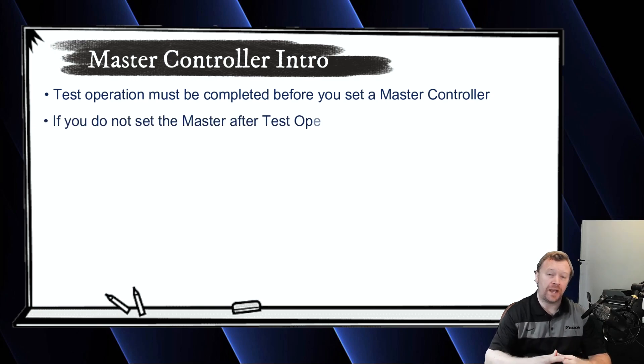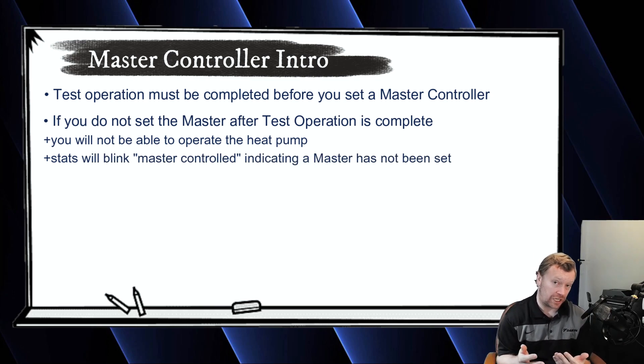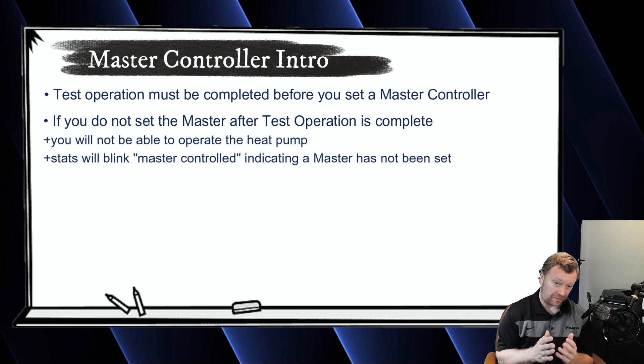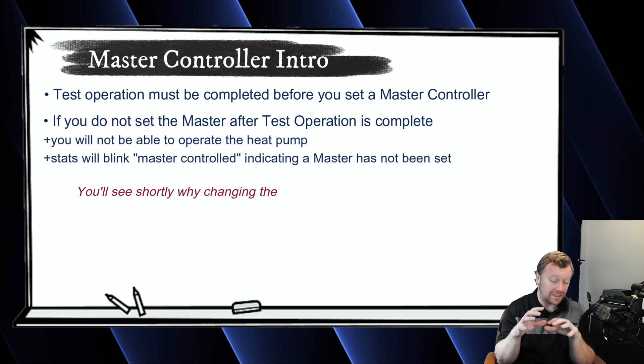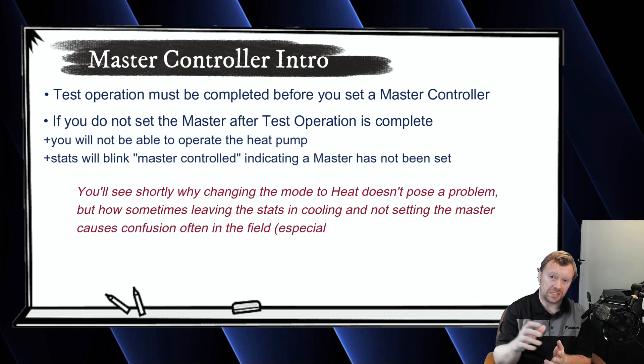If you don't set a master and you just turn on all the stats, they defaulted to testing cooling. So if you simply turn them on and don't change the mode, you only change the set point, the outdoor unit doesn't know who the boss is, so the outdoor unit will never turn on. I've had a few different jobs go down like this in the summertime, especially in my market, because that's when we cool — in the summer. We're cold in the winter in Seattle, so we always naturally change the thermostats to heat. In the summer, guys just see cooling as the mode out of test, and they think they're just going to turn it on, set the set point down to 67 or 68, and start operating the equipment. Nothing turns on and they call and ask what's going on.